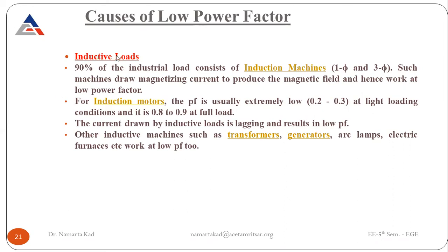So the first cause for the low power factor is the inductive loads. And 90% of the industrial load consists of induction machines, both in the form of single phase or three phase. Such machines draw the magnetizing current to produce the magnetic field and hence work at low power factors. So the main reason behind the low power factor is the inductive load present in the industries. For induction motors, the power factor is usually extremely low, like 0.2 or 0.3 at light loading conditions, and it is 0.8 to 0.9 at full load conditions.